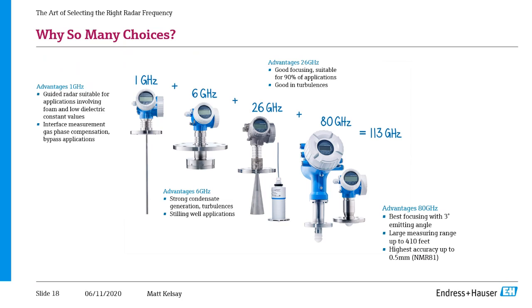The first is an interface measurement. So if you've got a separation type process, where you've got maybe the most typical is an oil layer on top of water, with a guided radar, we're able to measure both that oil level and the water level all in one device. The other is if you've got very high pressure and temperature applications, most notably would be a steam boiler. We have what we call gas phase compensation available on radar devices. It just makes them much more accurate in those high pressure applications, whereas a non-contacting radar would see a large degree of error.